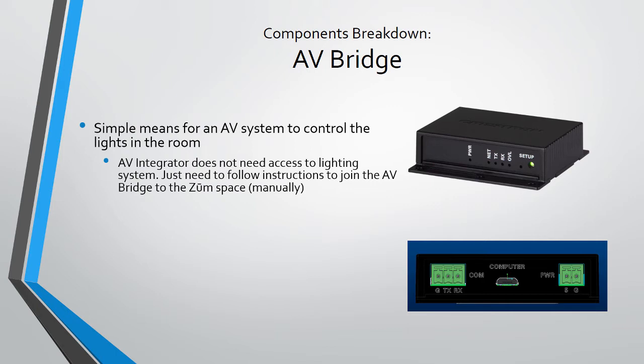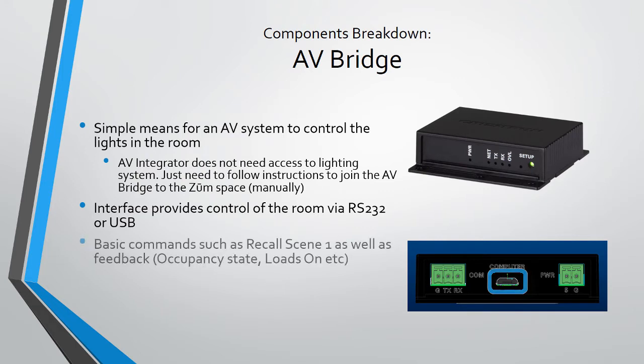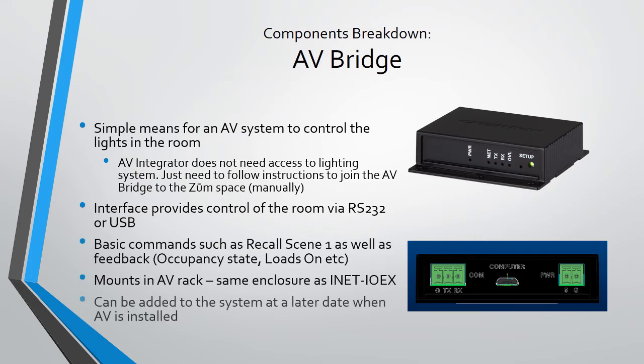The AV bridge is similar to the network bridge in that it allows anyone with an RS-232 port to control a Zūm space and perform simple and advanced actions. It's the easiest way for an AV integrator to gain control of the Zūm area. You can also communicate with the AV bridge via the micro USB port. Example actions include recalling scenes, getting occupancy state information, turning on specific loads, and much more. This device is very small and can be mounted locally in the room or in an AV rack.